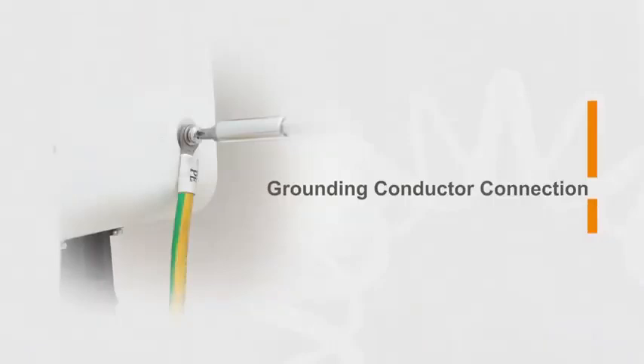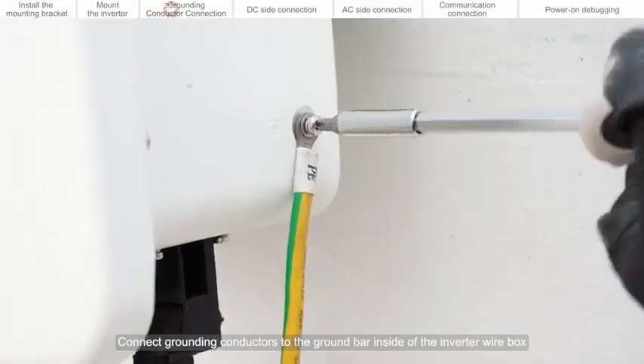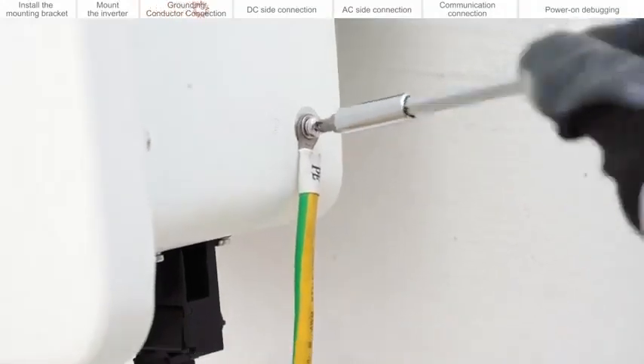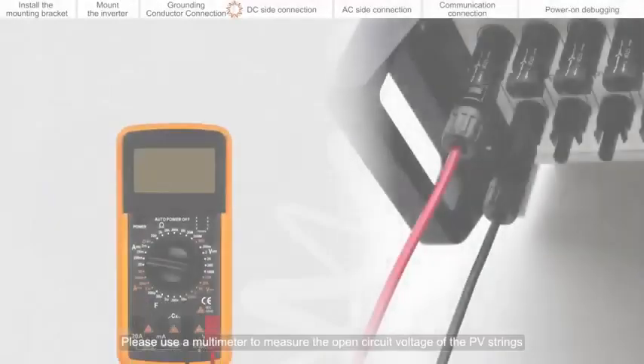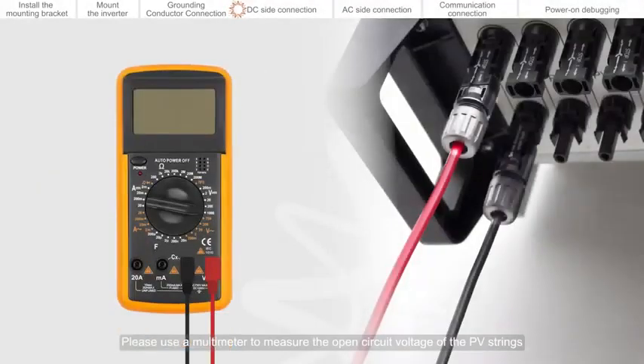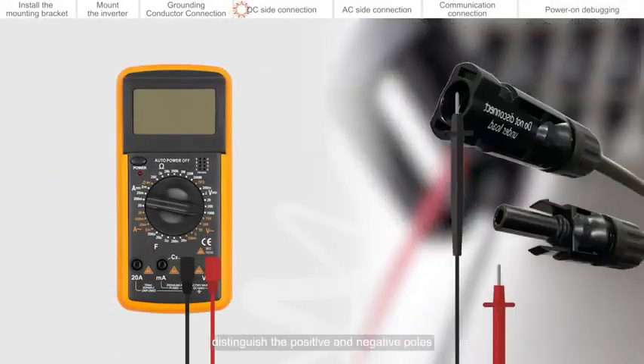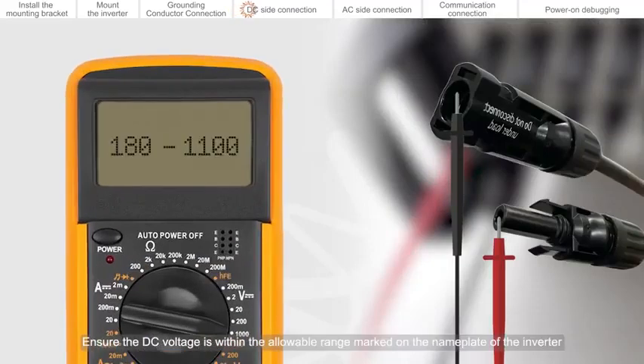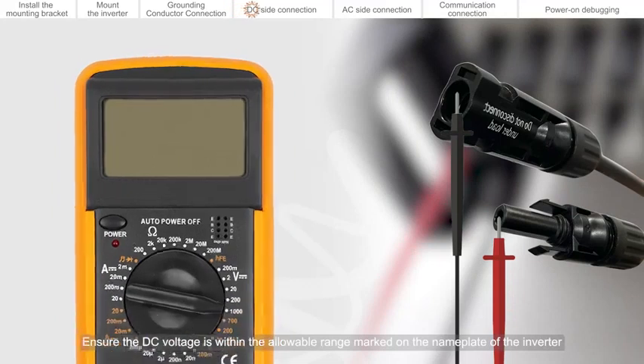Grounding conductor connection. Connect grounding conductors to the ground bar inside of the inverter wire box using a Phillips screwdriver. DC side connection. Please use a multimeter to measure the open circuit voltage of the PV strings. Distinguish the positive and negative poles. Ensure the DC voltage is within the allowable range marked on the nameplate of the inverter.